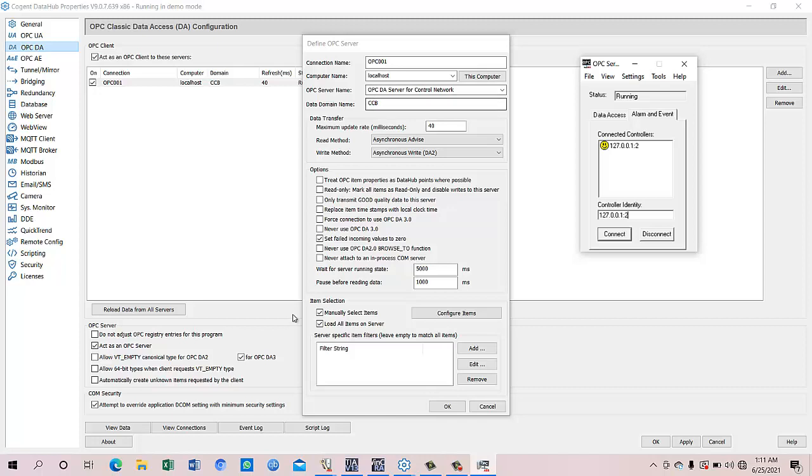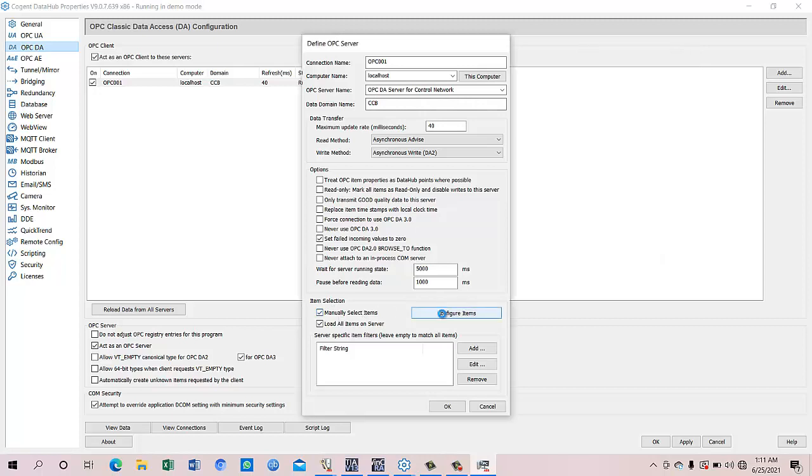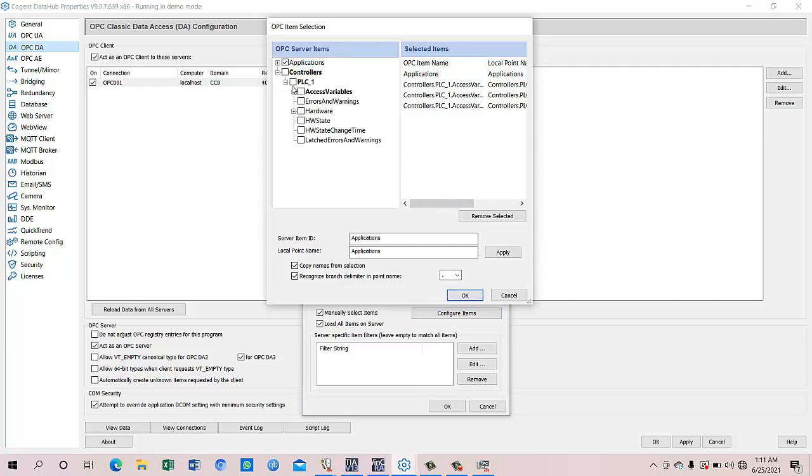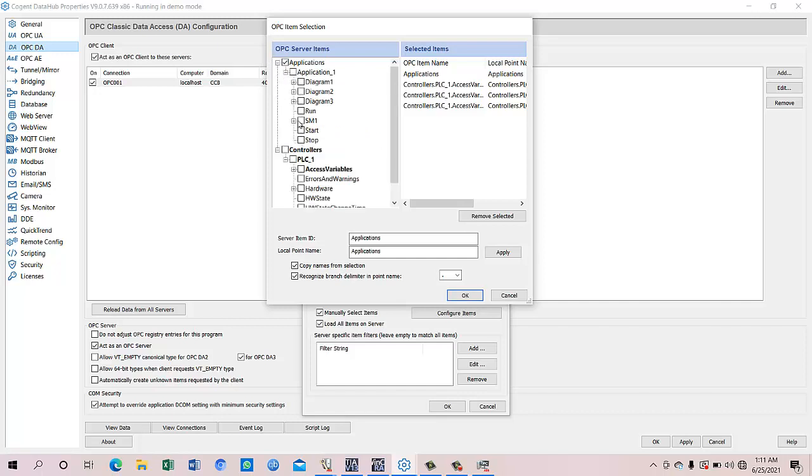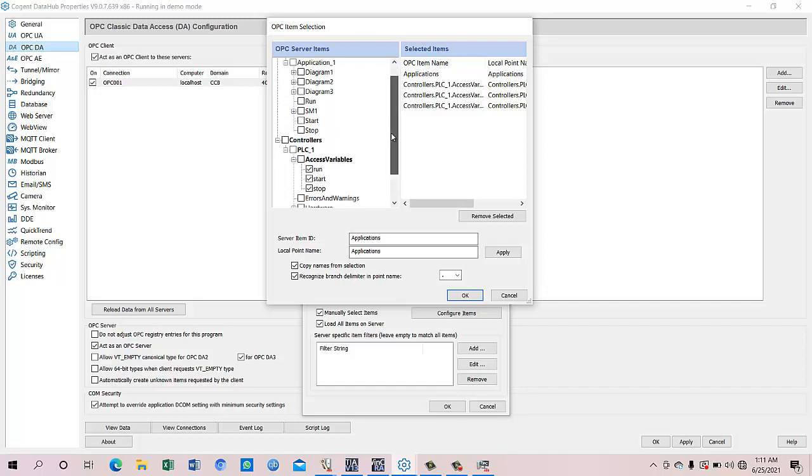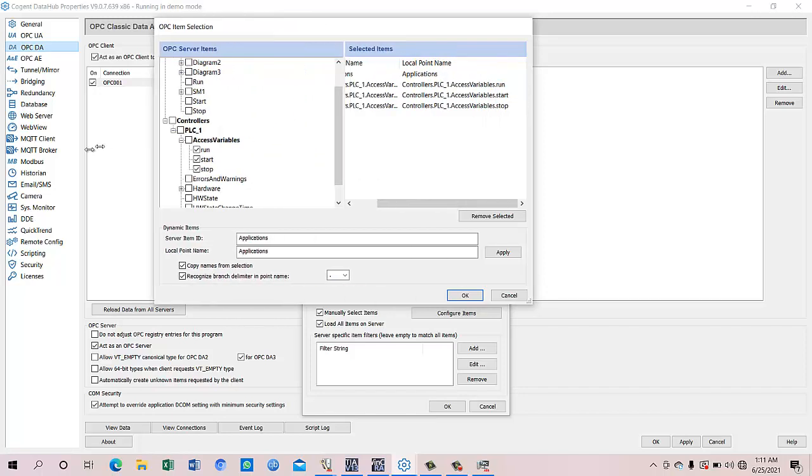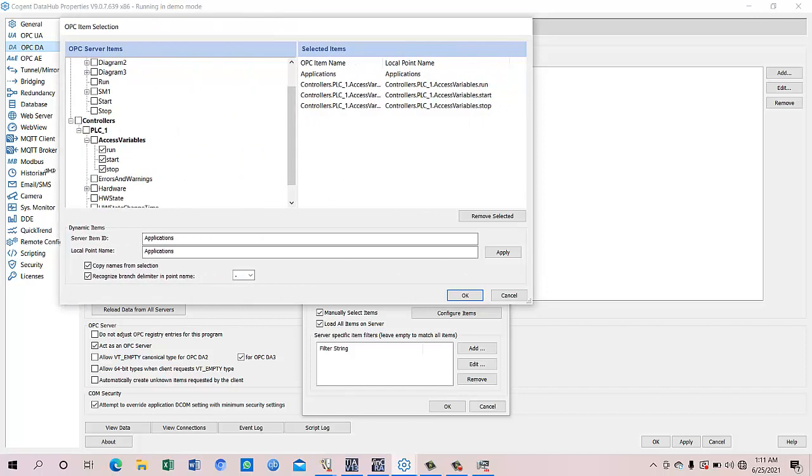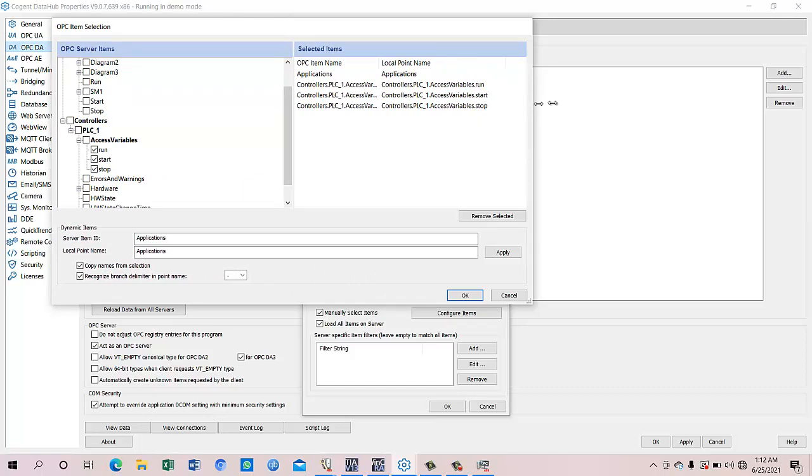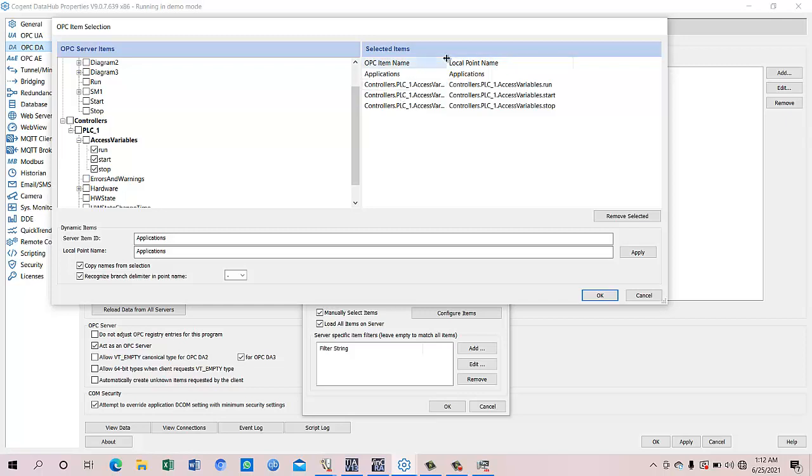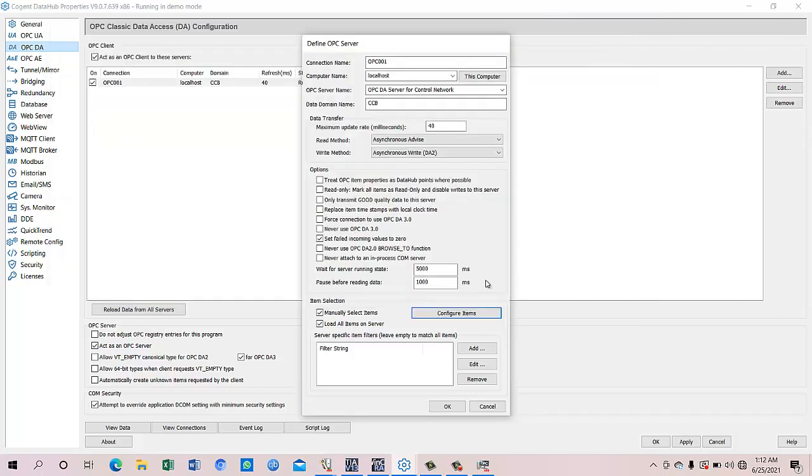So manually we selected the items. We did not select all the items. Here you can see the application, it is already connected and we did not take all from the application. We took only from the access variable. We connected to some of the starters, run, start, and stop. We connect this and it came as, so when we connect this it will come up to the right side of this window and we can see OPC item name and local point name. Now it's the same.